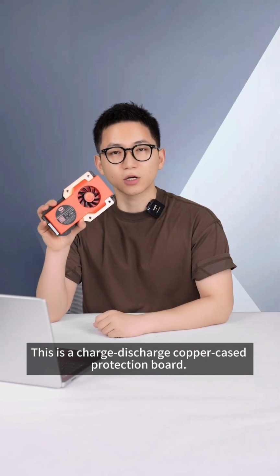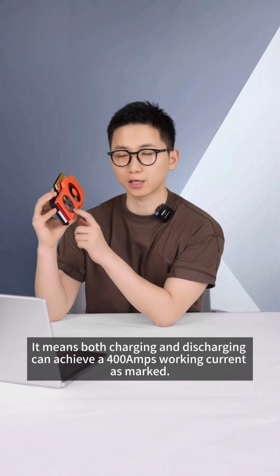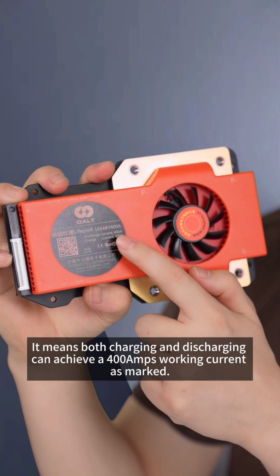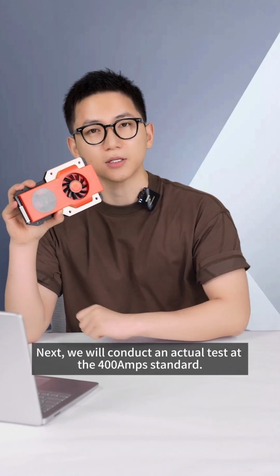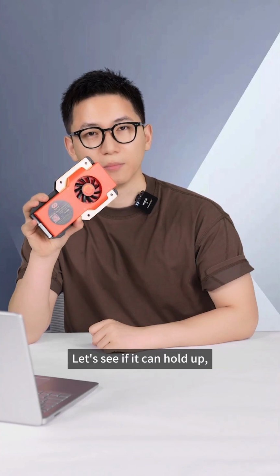This is a charge-discharge copper case protection board. What does that mean? It means both charging and discharging can achieve a 400 amps working current as marked. Next, we will conduct an actual test at the 400 amp standard. Let's see if it can hold up.